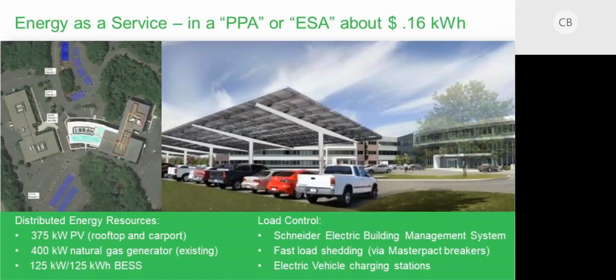So in this solution, we created 375 kW of solar power through rooftop and the carports. The building had an existing generator that was installed to back up a data center environment within this building. It was 400 kW, and then we later installed 125 kW of battery energy storage, which will be able to take that solar power when it's not being used to drive down carbon emissions or drive down the grid utility consumption, and to provide some energy storage and backup. Next slide.